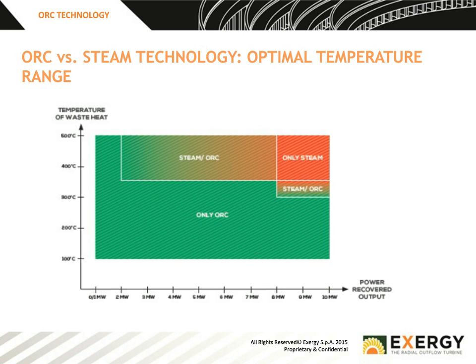So let's talk about a lot of gas turbines, for instance. If I'm talking about a 50 megawatt gas turbine, it's very likely that steam will be the more efficient and the more cost-effective way to generate electricity. However, if we're talking about a group of engines with an exhaust temperature of maybe 300 to 400 degrees centigrade, it's very likely that ORC is the more efficient, economical, and simple way of doing that. Same goes for the industry. It depends very much on the temperature, it depends on the complexity, and it depends on the size.